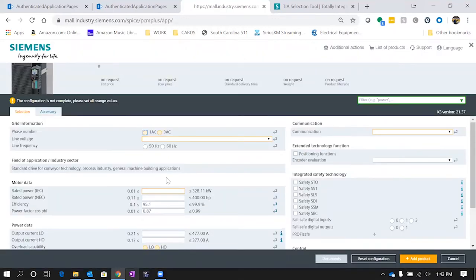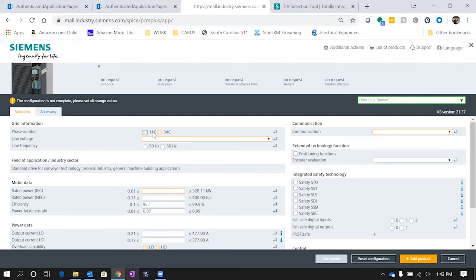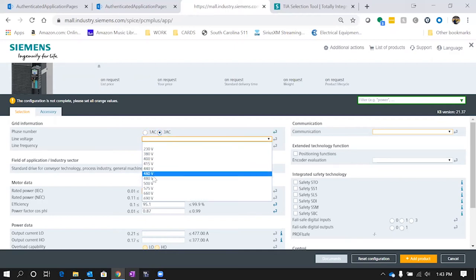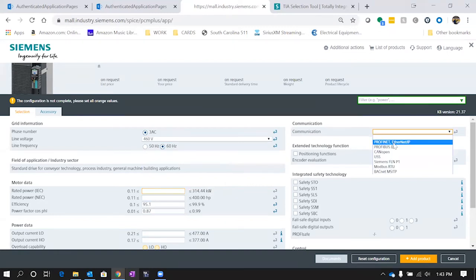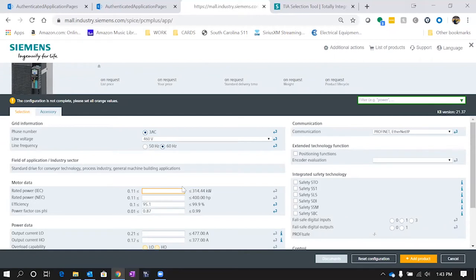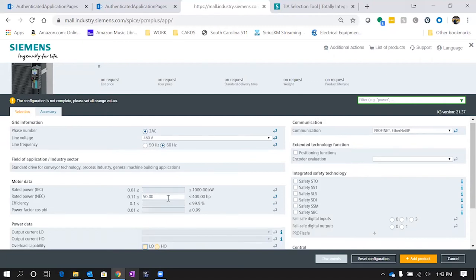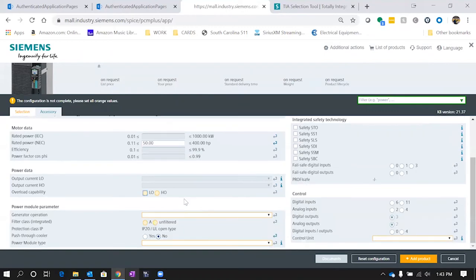Now that screen's up, we're going to see a whole lot of different options we can select. The most important thing to pay attention to is orange fields. Orange fields are required to be filled out. We're going to select three phase. We want 460 volts and 60 hertz here in the United States. For communication, let's select Profinet Ethernet, and you'll notice the tab goes to the next orange selection. It's asking for kilowatts. You can go to the next field even though it's white, not orange, and type in our 50 horsepower, which takes care of that section.